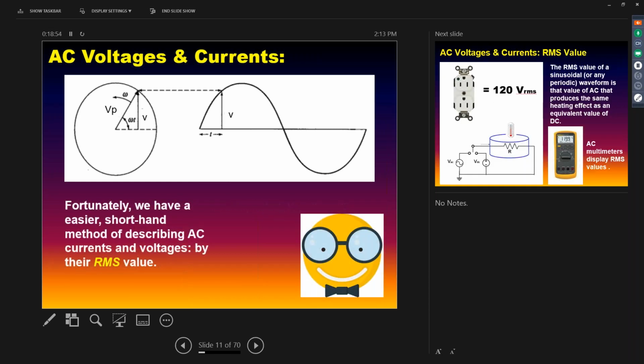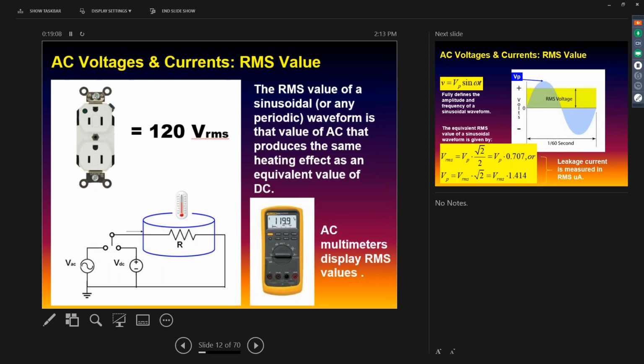Fortunately we have a simpler shorthand method, the RMS value of the waveform, root mean square, much more straightforward. This is what our multimeters measure: an AC multimeter or AC milliamp meter displays current and voltage in RMS values. Your safety analyzers display microamps in RMS as well, and this is also sometimes called the effective value.